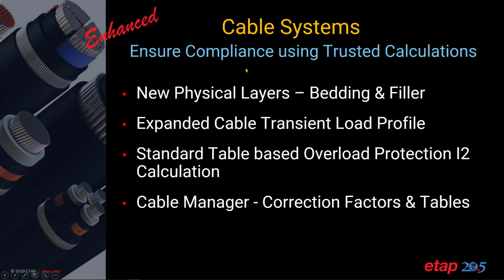The cable systems in ETAP have been enhanced to ensure further compliance using the trusted calculations that you expect from ETAP. The cable model itself has been expanded to include new physical layers such as bedding and filler. We've expanded the cable transient load profile to handle additional points, taking you into the 24-hour profile. We've also added standard table based on overload protection or I2 calculation. And we've expanded the cable manager to include the correction factors and tables from various cable sizing programs.